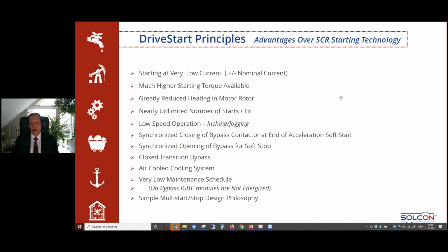So the principles are, we are starting at very low current. In most applications, maximum nominal current. Okay, it's different if you have, let's say, a ball mill, then it is higher. We have much higher torque available. We are reducing with this the heating in the motor rotor. Remember what I said in the beginning, you have a very high starting current with asynchronous starting. And with this, you have a nearly unlimited number of starts per hour. It is a little bit limited.